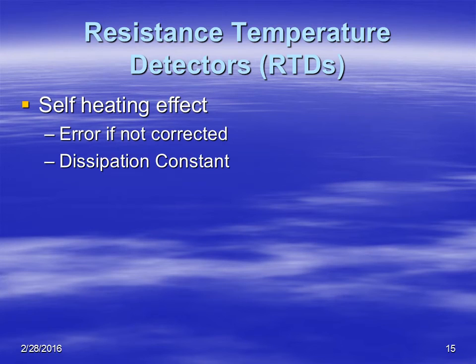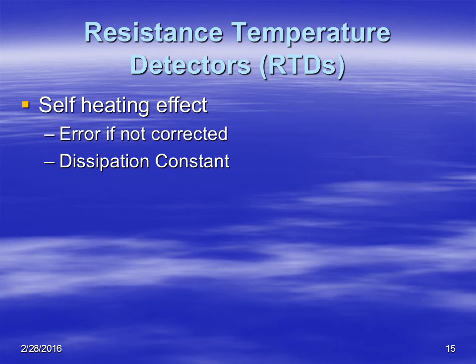Another problem with RTDs is that anytime you're running a current through a wire and there is some resistance, you're actually heating up the wire a little bit — much like a toaster. When you plug in a toaster, you're running current through heating elements. Even a conductor will heat up as you run current through it. So there is some error introduced because of the heating effect of the conductor, but typically that can be corrected using a constant in the calibration.